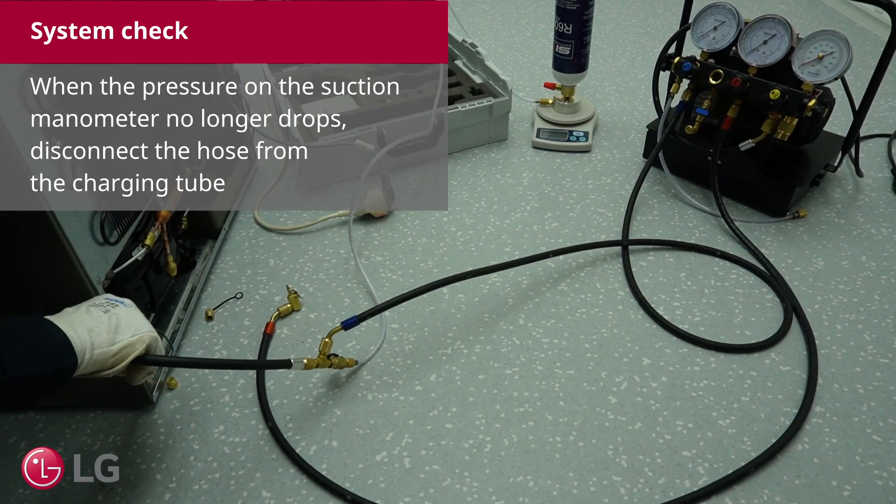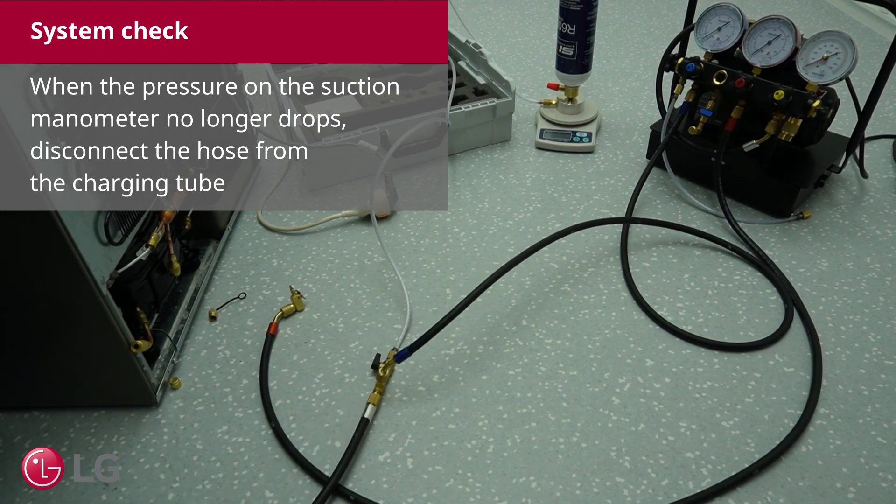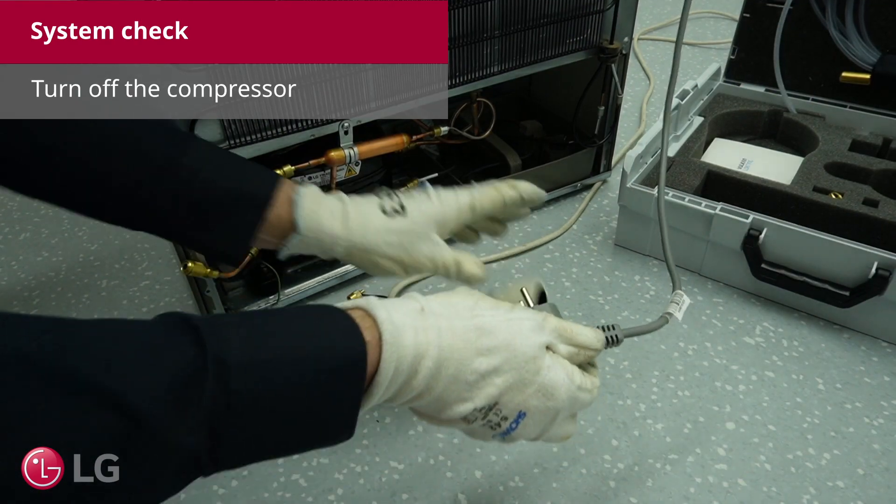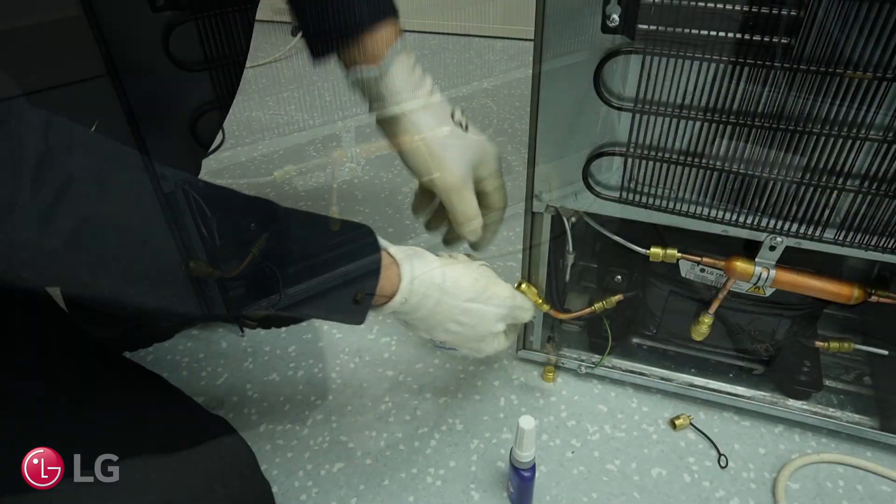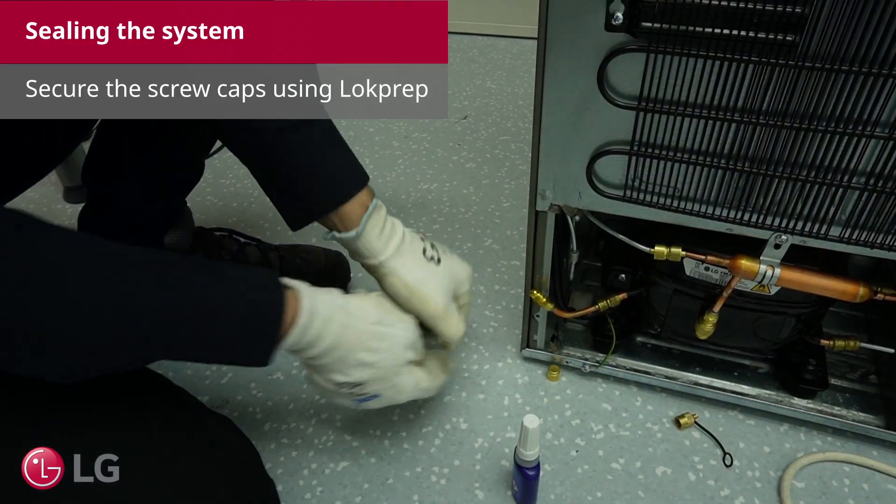When the pressure on the suction manometer no longer drops, disconnect the hose from the charging tube. Turn off the compressor. Secure the screw caps using Lokprep.